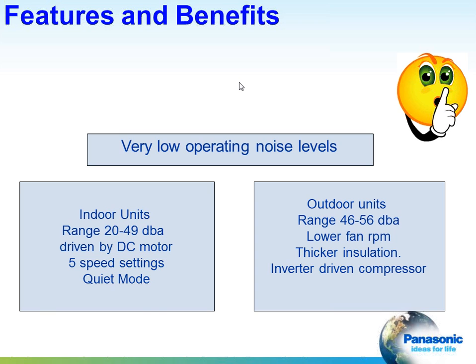We have very low operating noise levels. The indoor units are driven by DC motors, multi-speed, and the dBA range that we're going to achieve there is 20 to 49. The outdoor units are very quiet too. Lower fan RPM is possible because we have a better designed fan blade, which allows those lower RPMs, which makes it quieter, and thicker insulation in the condenser unit cabinet or the heat pump cabinet. And again, that inverter-driven compressor is a slow start, so you don't have the bang that you might experience with a typical scroll compressor.